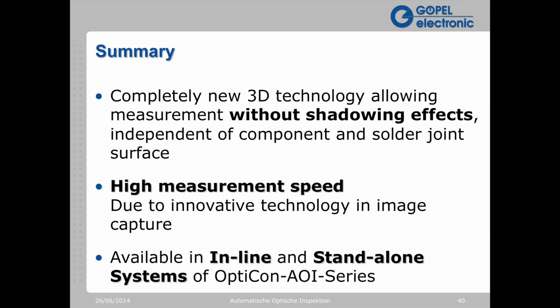completely new 3D technology which allows measurement without shadowing effects and completely independent of component and solder joint surfaces. Whether the surfaces are reflective or absorptive, our multi-spot array is able to project a lighting, and our camera systems are able to detect reflections from that lighting and interpret the Z dimension depth.